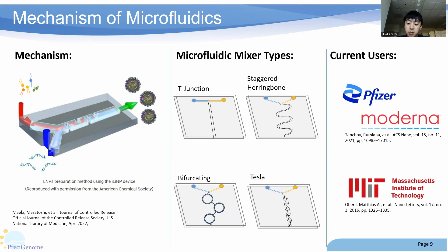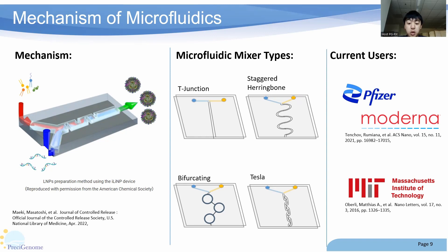In the middle section, we can see the common micromixer geometries used today. Starting from the top left, we have the T-junction, a widely used design where two fluid streams intersect at a T-shaped junction, inducing rapid mixing due to shear forces at the interface. The staggered herringbone to the right uses a pattern of herringbone-shaped grooves, generating secondary flows that result in effective mixing. At the bottom left, we have bifurcating mixers, which have multiple inlets and outlets, promoting intricate fluid mixing through repeated bifurcation and merging of the streams. The Tesla mixer is very similar in principle to the bifurcating mixer, and is actually what PreciGenome uses for its own microfluidic chips.